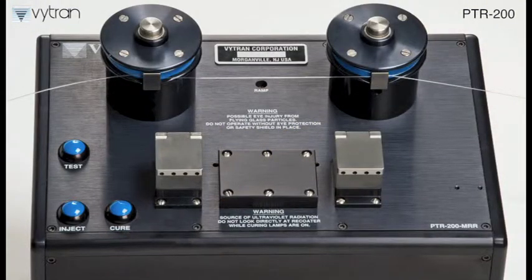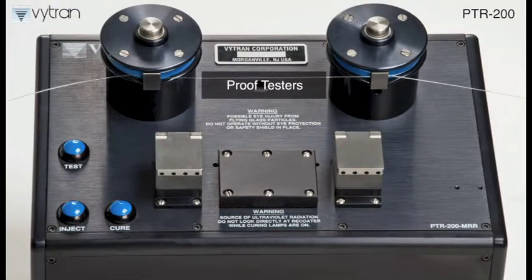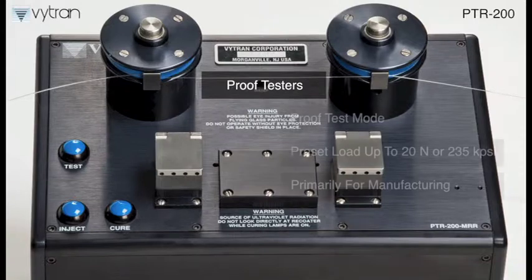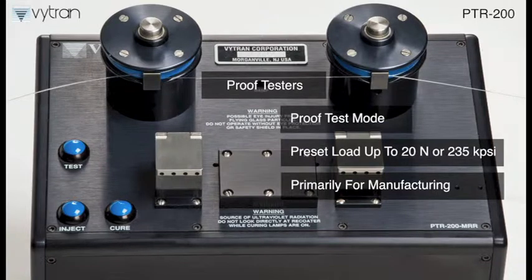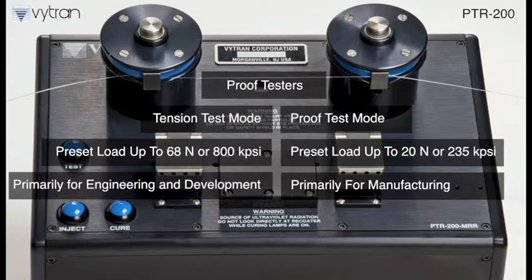Vytran's PTR-200 proof testers apply a set load at a controlled rate to an optical fiber or fusion splice. These loads can be taken up in two ways. In proof test mode, the load is taken up to a predetermined level and released. In tension test mode, the load can be taken up to the breaking strength of the fiber.